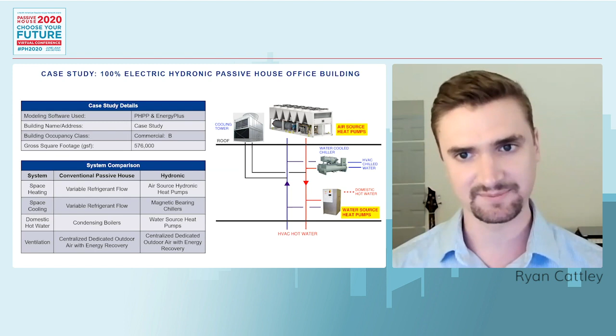So whenever there is simultaneous building heating and cooling demand, which in an office building you will generally always have, a year-round cooling demand due to the high internal loads typical to an office building. In those instances of simultaneous building heating and cooling, we can recover that rejected heat from the chillers. And instead of just rejecting that heat through our cooling tower out of the building, we can use it to actually help heat our building, which means that the air source heat pumps don't have to run as often or work as hard.